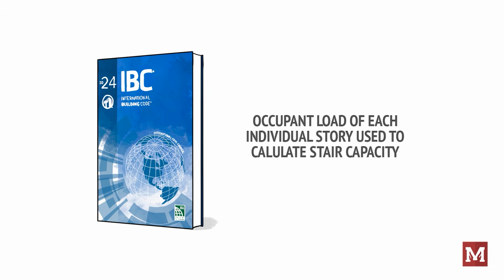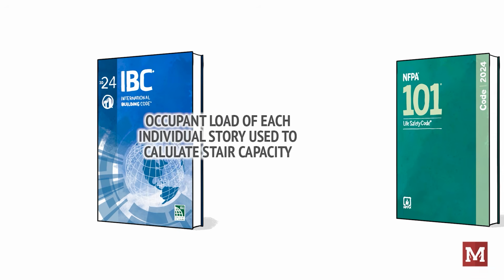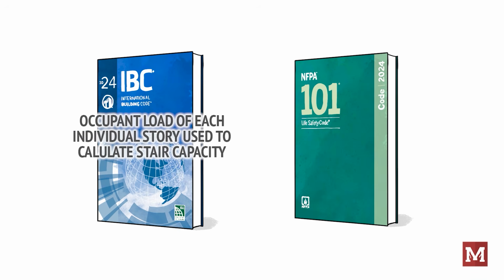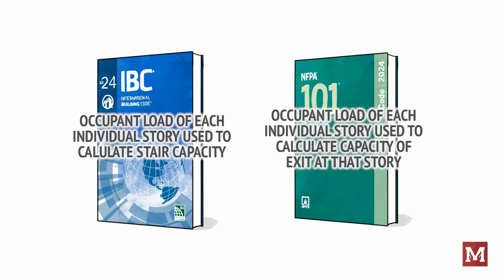NFPA 101 is even more explicit and states in 7.3.1.4 that only the occupant load of each story is used in computing the required exit capacity at that story. It also adds an extra bit, provided that the required egress capacity of the exit is not decreased in the direction of egress travel. That extra part is something called egress width continuity, which we'll discuss in a later video. So we look at each story individually.